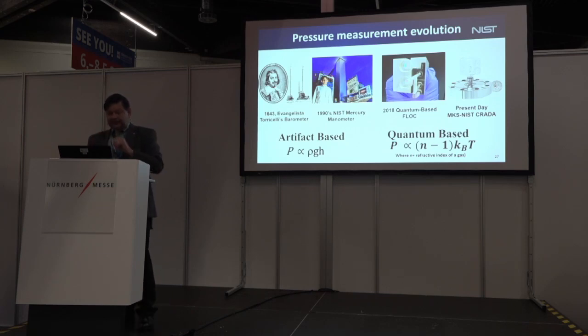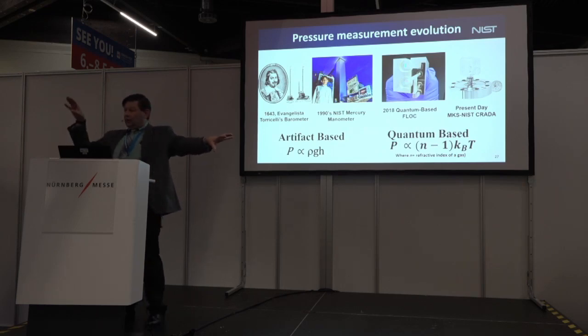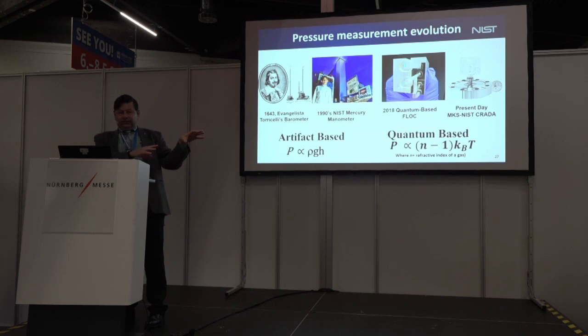But just to continue with this slide, what you're seeing is a transition from the artifact-based really over to the quantum-based. So in the artifact world, the pressure that you're going to generate is called rho g h. Rho is the density of mercury, g is the constant of gravity, and h is the height. But now in the quantum-based system, it's the refractive index of the gas that's in one of the cavities, the Boltzmann constant, and the measured temperature. Boltzmann constant is fixed now, so all you need to do is make an ITS-90 measurement, because we're still using ITS-90 in the lab, and you've got your measurement of pressure.